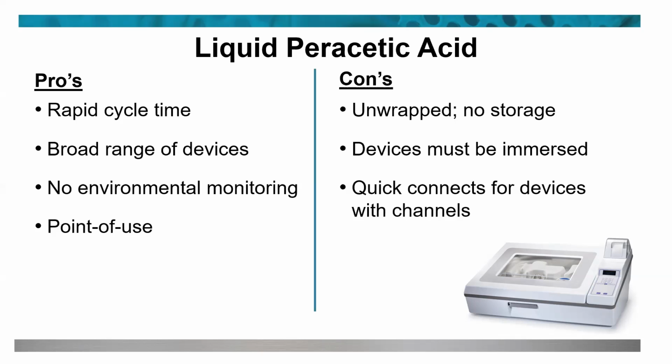The cons, again, it is unwrapped. There's no storage system on there, so it's for just-in-time use. You have to use devices that can be immersed. We want to make sure that it's going to be in liquid, so you're going to have to be able to immerse all the devices. And then if you're looking at endoscopes and stuff, not all the quick connects are available for everything with channels in them.